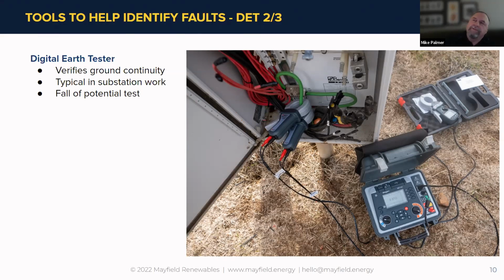If you're looking for a solution that has all of our ground testers, because you never know what you're going to need, this will do everything: soil resistivity, 2, 3, and 4 probe testing, and fall of potential, which we'll talk about in a minute. But really, in the substation, we can use the clamps to go element to element, switch to switch, on the grounds in the substation, and just measure continuity there and see the low resistance that's encountered. If the resistance is higher, then we know we have a problem on that particular switch or stanchion.